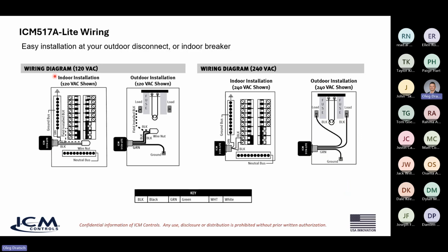So, wiring the device. Again, it's ready for 120 volt AC. Coming out of the device are 2 black wires and a green ground wire. In this particular application for indoors, you would cap the 2 black wires, install another wire into the circuit that you want, and then also ground the green wire onto the ground bus. For an outdoor application, again, capping the 2 black wires, running another wire to the field installed black, and then your green goes to ground. For 240 volt AC applications, you can see the 2 black wires coming out of the device connect to the individual circuit breaker, and then the green goes to the ground bus. And then for outdoor, like for an HVAC unit, these devices connect onto the load side. So black to one load, another black to the other, and then green to ground.